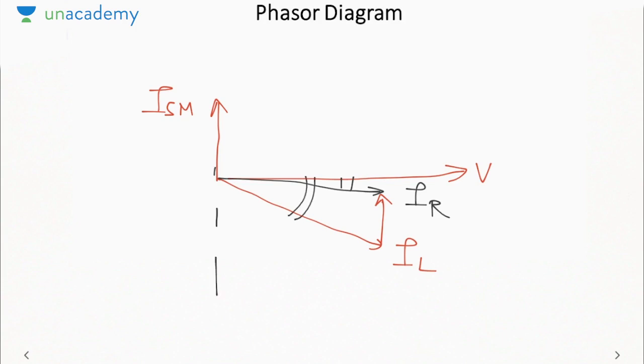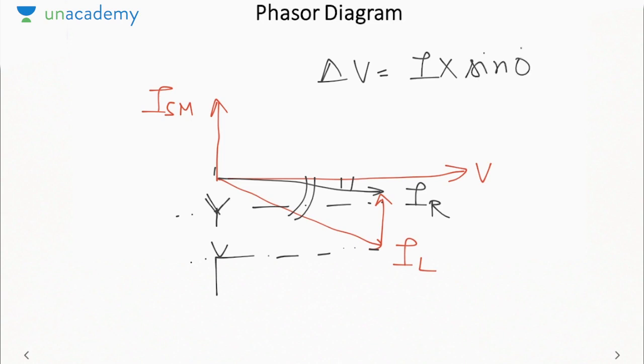And as we saw in the shunt capacitor, the vertical component of the current reduces, that means voltage regulation or voltage drop reduces, because voltage drop was I X sin phi. So it was depending on sin phi, that is the vertical component of the current.